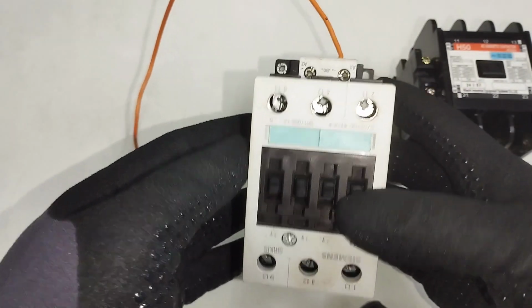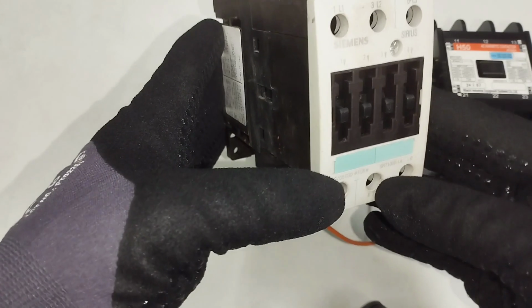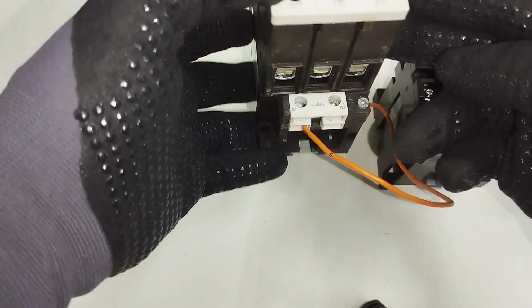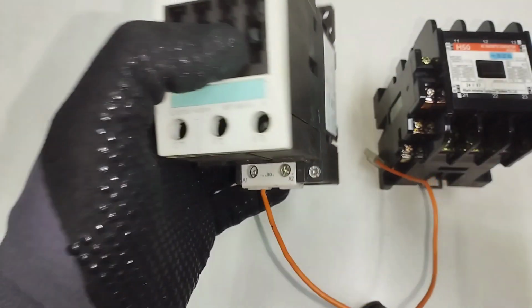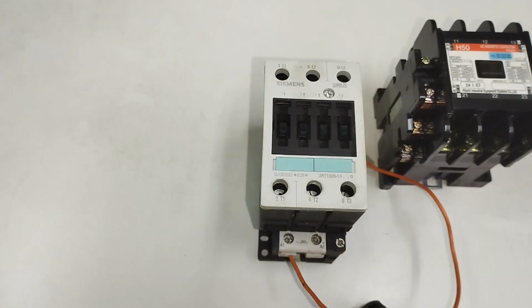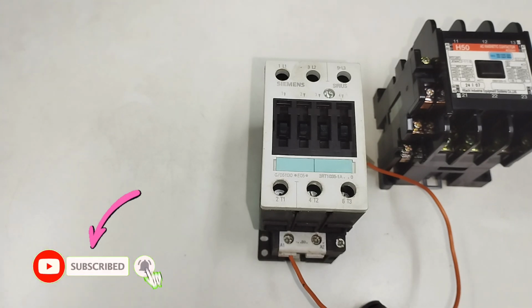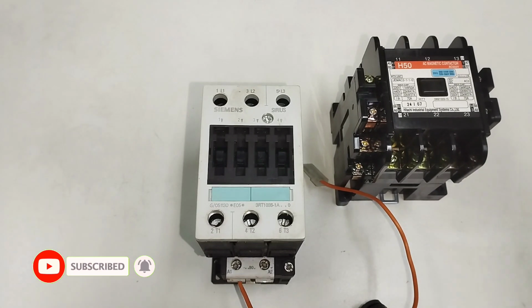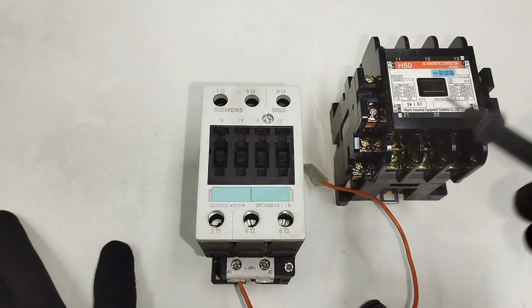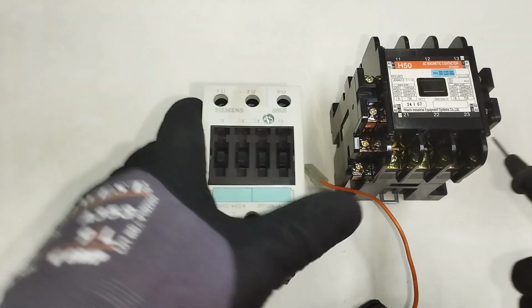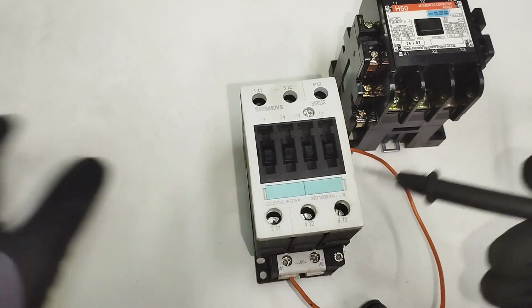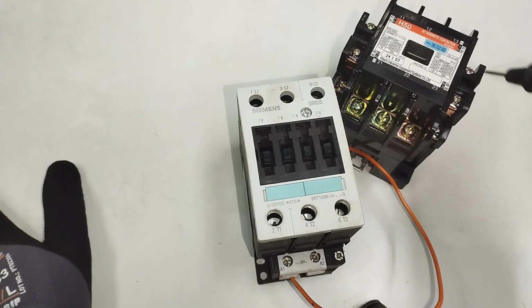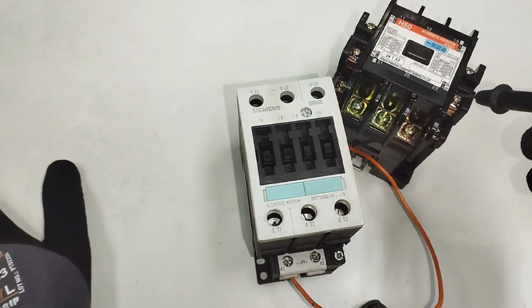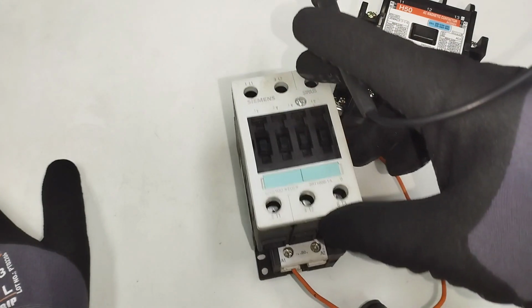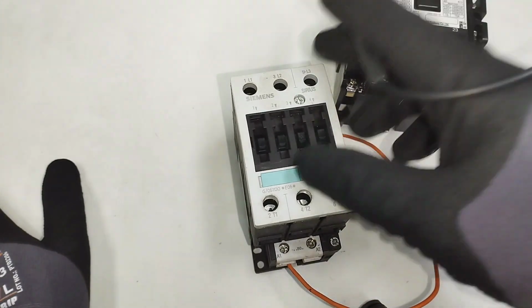Now, looking at this video, you notice that this contactor is a little bit different from this. And what is the difference? If you look at the contactor critically, though if we did not explain, you might not really know the difference. Number one, aside from the manufacturer, you notice that this contactor does not have auxiliary contacts. Like this one has auxiliary contact, like we were saying, normally close and normally open contact. But this does not have normally close. It does not have auxiliaries.